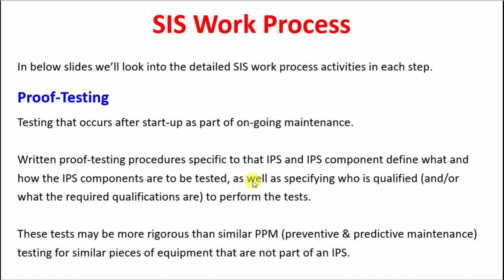Written proof testing procedures specific to the IPS, instrumented protection system, and IPS components define what and how the IPS components are to be tested, as well as specifying who is qualified and what the required qualifications are to perform the test. It's not that any instrument technician or electrical technician can go and do the maintenance on such instrumentation. They have to have a certification. They have to undergo the criticality requirements of the particular instrumentation and shall be able to do all kinds of testing required. So there could be some certification requirements for those maintenance technicians or supervisors who are involved in the plant maintenance.